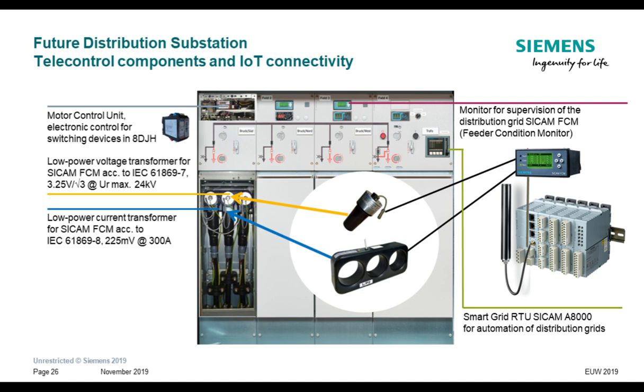We would also like to telecontrol the system, and for that we have the motor control unit. That is the left device, a small black box, which is also integrated in the 8DJH, and it's also modular. That means we control each bay via this motor control unit, which is connected not physically by hard wires to our SICAM A8000 RTU. No, it communicates via protocol, via Modbus protocol for example, which is quite simple and easy to adapt. This flexibility is used in each and every bay, so we can immediately send direct commands to the different bays to switch on and off, and to telecontrol these bays.